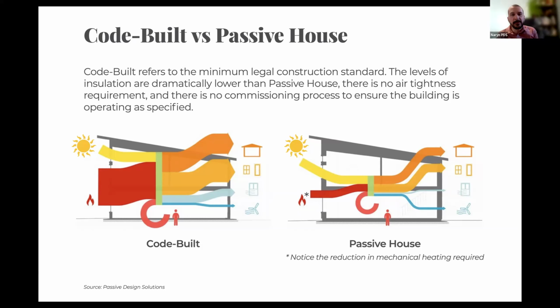In the passive house, the solar gain and internal gains are similar, but because the heating load is so much smaller, it's balanced on the right-hand side by envelope upgrades—less passive ventilation loss through an airtight envelope, less heat loss through windows and doors, since you've super insulated and eliminated thermal bridges. These diagrams come from a custom home we designed that was built in PEI, and this energy modeling looks at how to reduce that heating load, since it informs the envelope decisions and the sizing of the mechanical system.